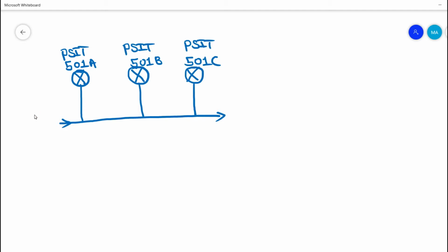So we have a process gas flow which is getting into this pipeline, and if the pressure gets low, that is PSLL. So if the pressure gets low, we have three independent transmitters, and if the transmitters sense the pressure low, it would generate a trip action. Here we are using 2 out of 3 voting logic for these Alpha, Bravo, Charlie transmitters. So totally we have 3 transmitters, and we're using 2 out of 3 voting logic over here.